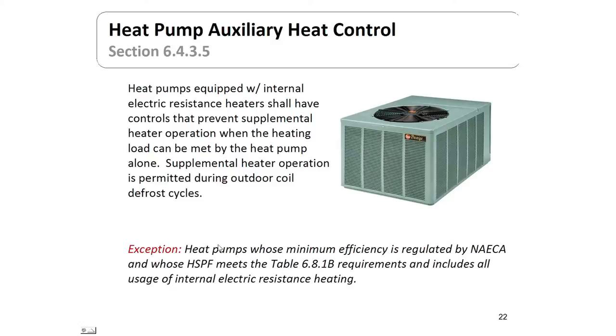On heat pump auxiliary heat control: heat pumps equipped with internal electric resistance strip heaters need controls that prevent supplemental heating with that strip heater when the load is actually met by the heat pump compressor itself. The exception is heat pumps where the minimum efficiency is regulated by the National Appliance Energy Conservation Act and whose heating seasonal performance factors meet table 6.8.1B.